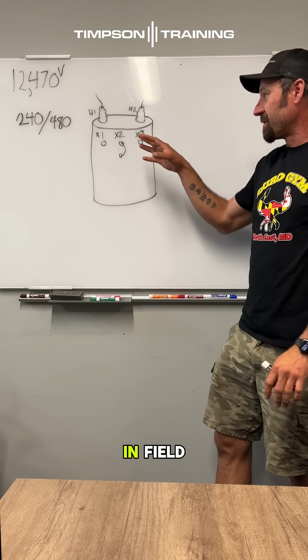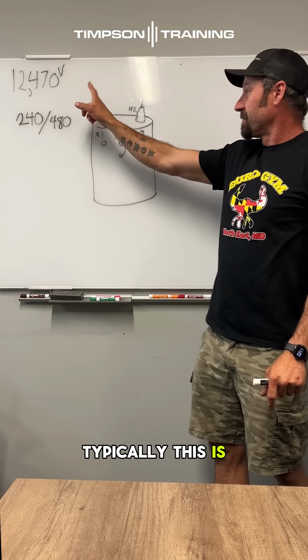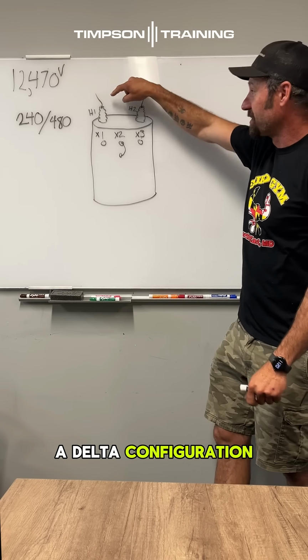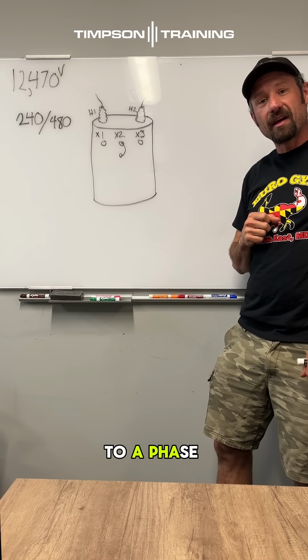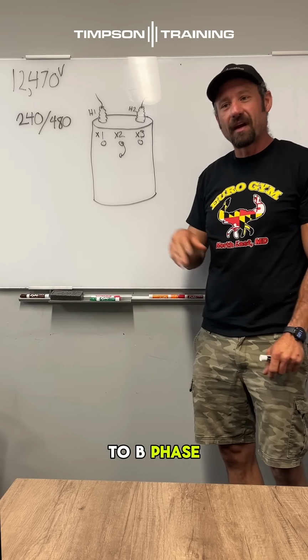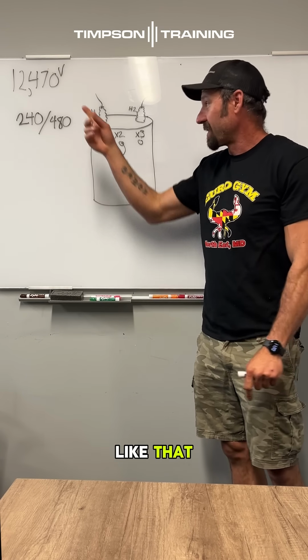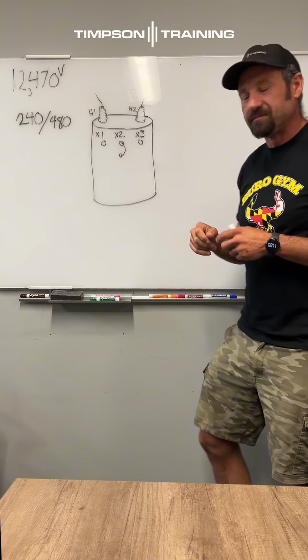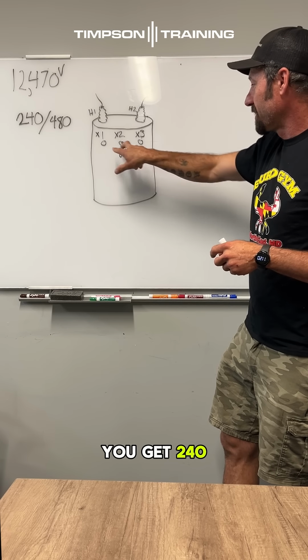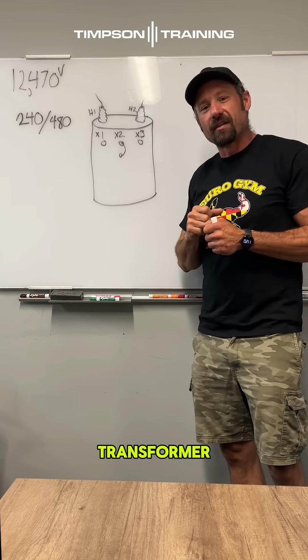If you ever see these in the field, typically this is hooked up in a delta configuration. H1 would go to A phase, H2 would go to B phase, or something similar. These two get hooked up to a phase, and you get 240, 240, 480 out of that transformer.